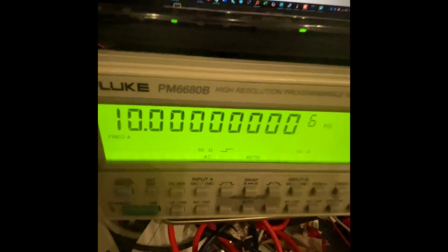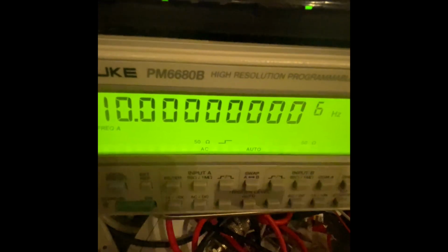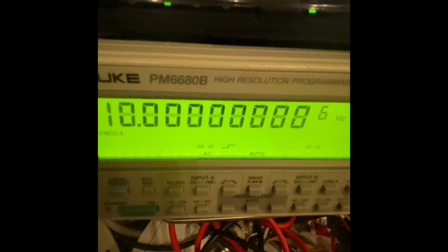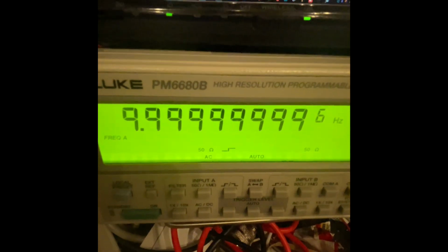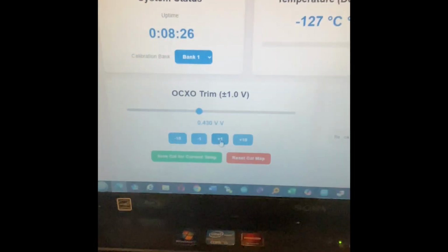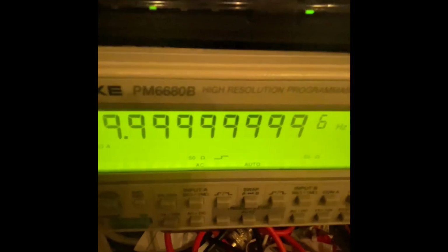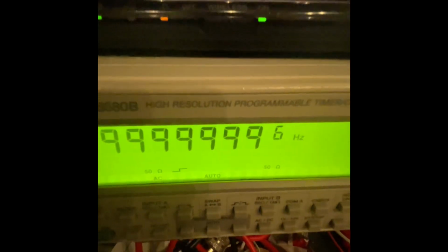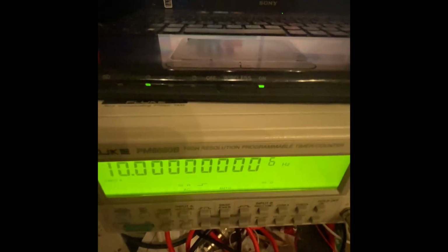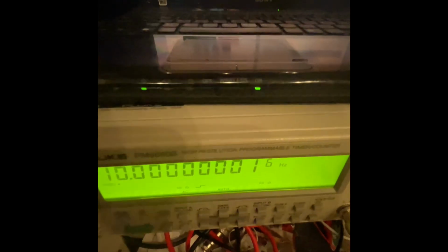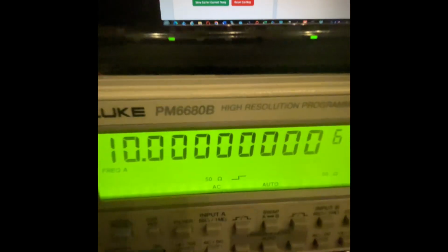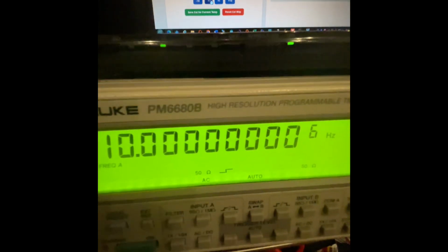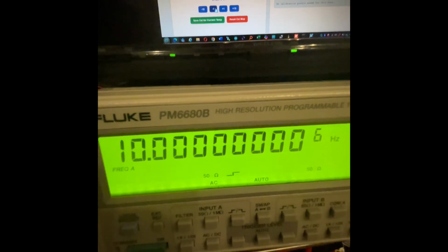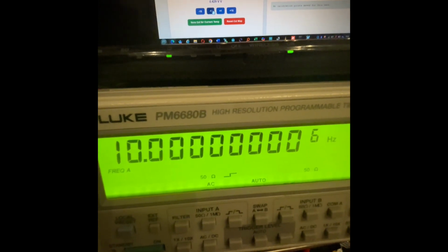So the oven hasn't actually warmed up properly yet, so we're going to get a bit of jitter there. But as soon as the oven settles itself down, it's only been up for like 8 minutes now. I'd expect that to be a little bit more stable after maybe 20, 25 minutes. There we are. So it's pretty good. We're working well. And it learns. So in essence, once the program's actually running and the temperature's actually noted, we'll never really need to even dive into the program at all in the future because it'll just simply keep the calibration and the frequency and everything all tuned to each other. There we go, 73s.